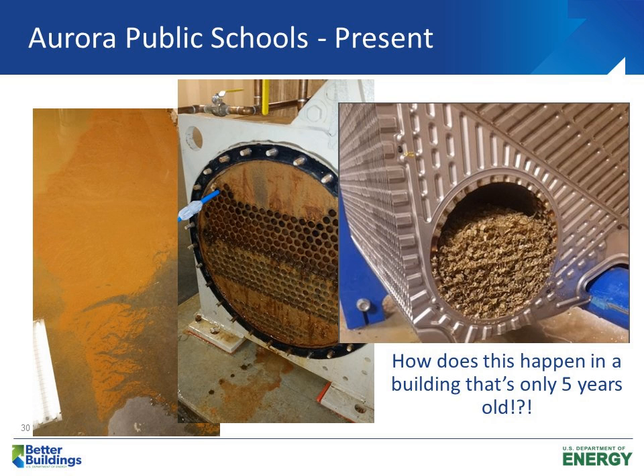So we come to another condition, kind of the back of the house of my bowling alley. We had a situation where we discovered a chiller was plugged full of debris from the cooling tower condenser water, and despite all efforts to clean the heat exchanger, as you can see on the right, and get rid of that debris, it literally filled up again in a matter of days. So how do we handle situations where we believe our energy consumption is curtailed as best we can, but there are inherent challenges in the energy use of the installed equipment?